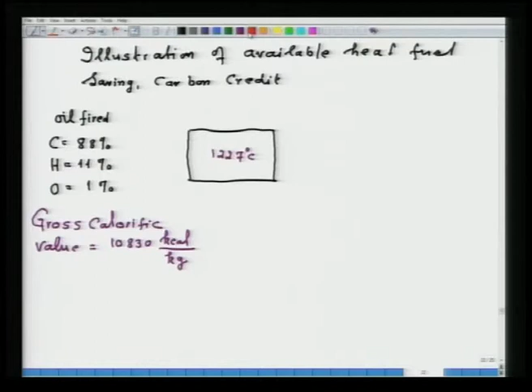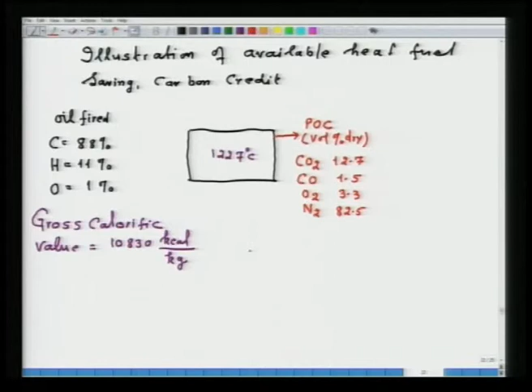The products of combustion, the POC, their percent is given by volume percent dry, and this composition is CO2, CO, O2 and nitrogen. CO2 is 12.7%, CO is 1.5%, O2 is 3.3% and nitrogen is 82.5%. It is combusted with air, and now we have to calculate the various available heat, fuel saving and so on. For this purpose, let us take 1 kg fuel as our basis of calculation.